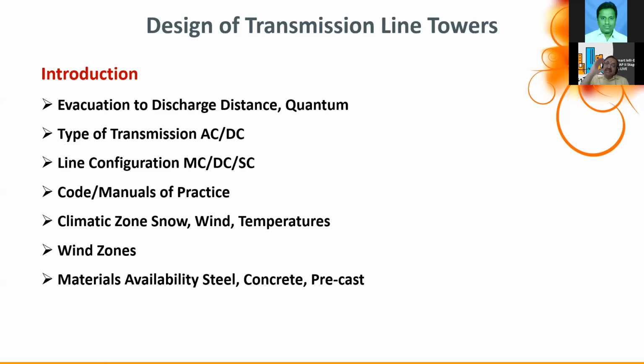And extra thing is temperature is critical in transmission. So climatic zones, the snow loads, and minimum temperature, maximum. In India, India is the probably only country where the temperature range is minus 30 degrees in north and northeast to plus 50 degrees. Highest can go up to 55 degrees in Rajasthan and all. So temperature, why temperature is important? Because we have these conductors in transmission, the spans ranging from 200 meters to 450 meters span. So imagine the elongation or contraction of the conductor, and at lower temperature, this conductor causes tension on the tower. It pulls the tower.